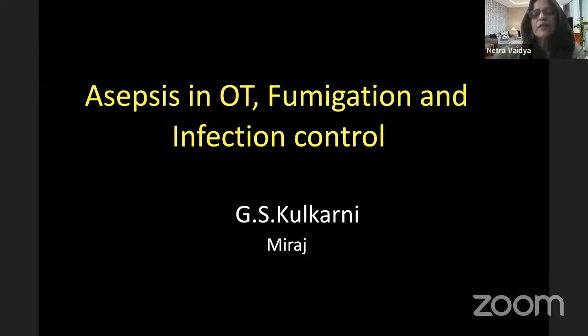Basically, the latest sterilizers have the capacity to introduce moisture. And the recommendation, if you use cannulated instruments, is to put some amount of water into them. It creates moisture within while your sterilization process is happening. Okay, so then it facilitates the sterilizer. But how much moisture you keep inside the cannulated instrument, we need to be very particular about it, because at the end we are going to get wet packs. Okay, so the mass density of the instruments and packs also has an effect on sterility.